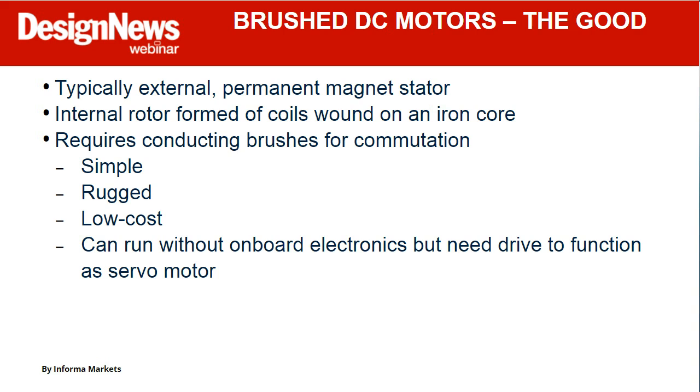They don't have to have onboard electronics, but that said, if you want to use them for precision motion, you're going to need a drive, and you're going to need feedback. That's kind of what puts the servo in servo motor.